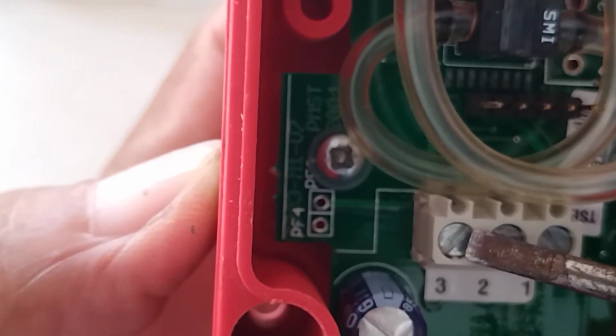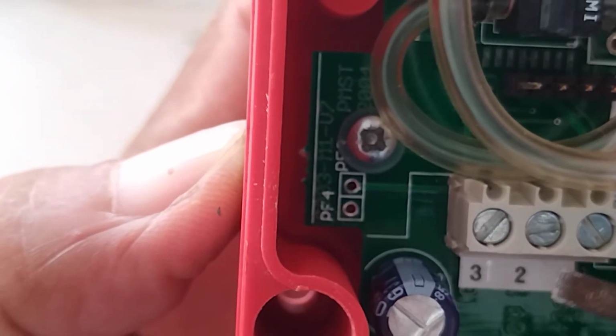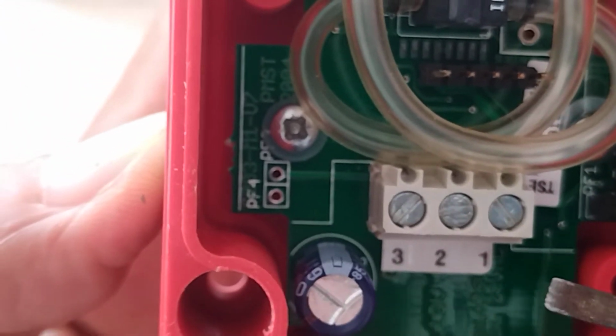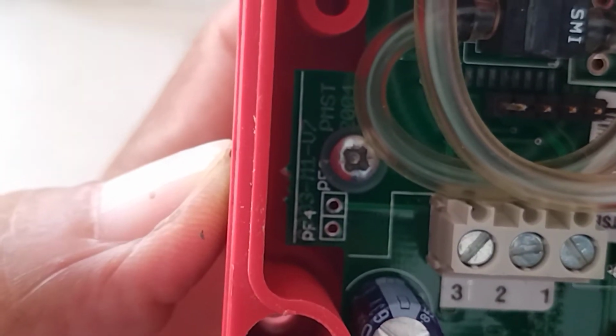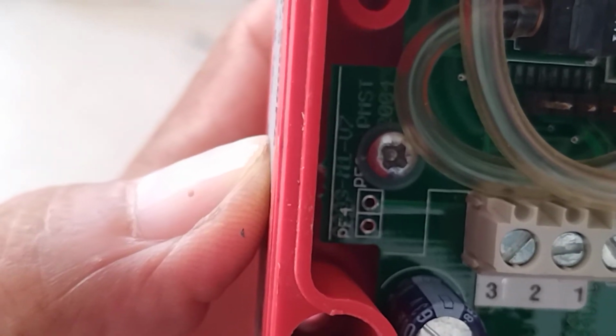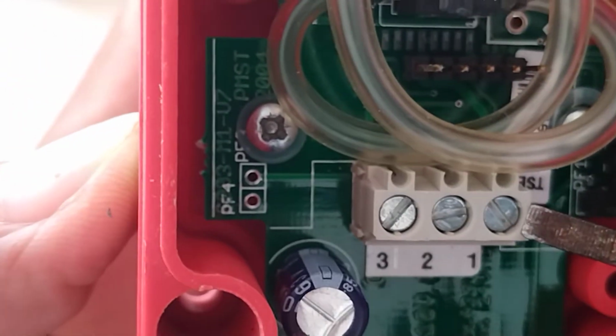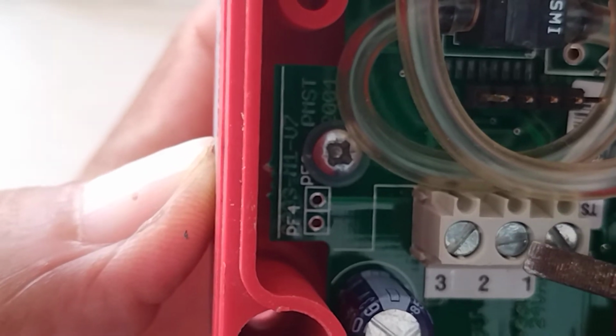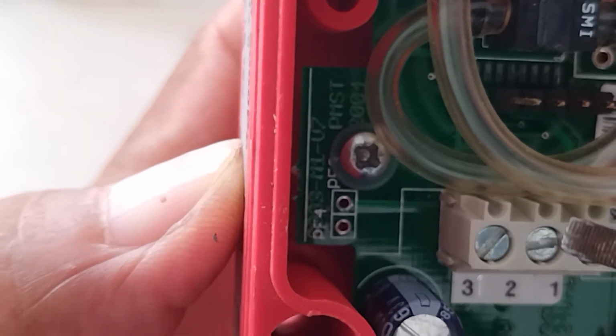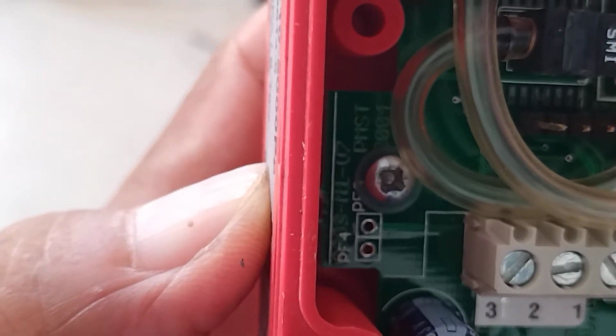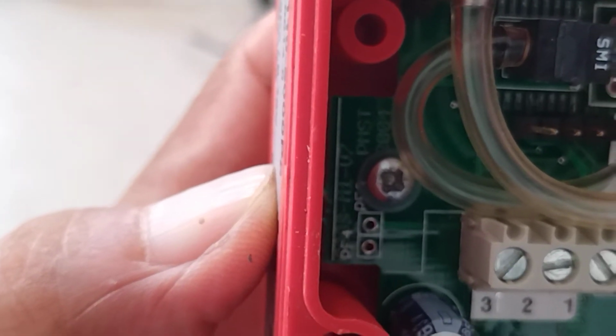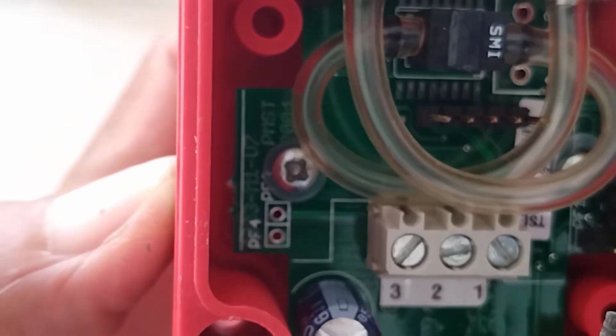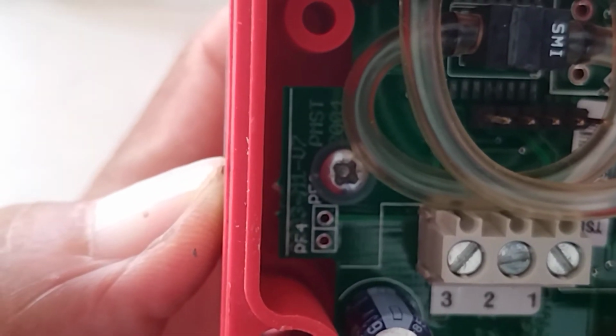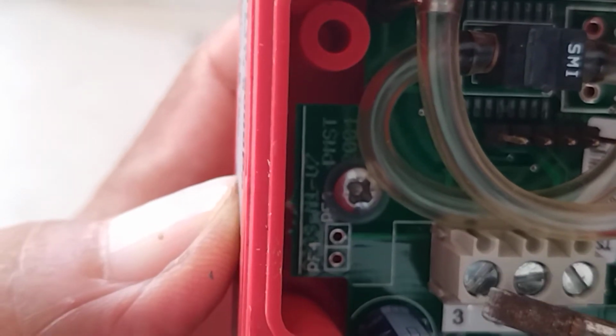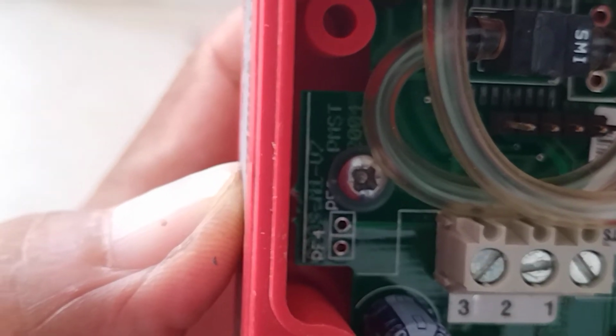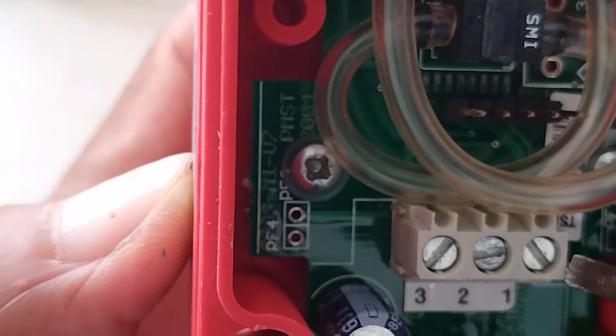You have 3, 2, 1, so you can pull a 4 core cable here. One wire will be the 24 volts, usually red. Then one wire will go to 2, and one wire will go to 3. The power supply of 24 volts will be 2 wires. If it's color coded, it will be black and red. Black is common, it will go here. Then the red, which is the 24 volts, will go here.